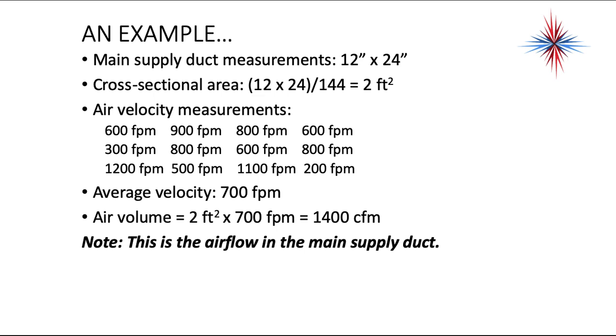Here's an example. Your main supply duct measures 12 by 24 inches — reasonable for a residential main supply duct. Multiply 12 by 24, then divide by 144 to get 2 square feet. You can't do this calculation in inches; you have to convert to square feet. We take multiple velocity measurements across the ductwork: 600, 300, 1200, 900, 800, 500, 800, 600, 1100, 600, 800, 200 FPM. You add those up and divide by the number of readings to get an average of 700 feet per minute. Multiply 2 square feet by 700 FPM to get 1,400 cubic feet per minute.